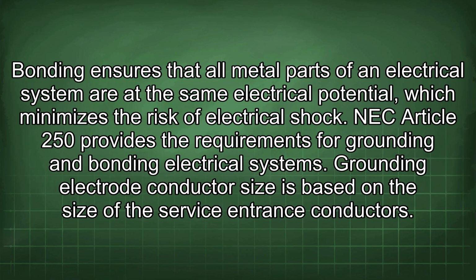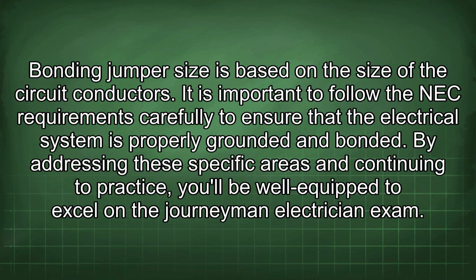Bonding ensures that all metal parts of an electrical system are at the same electrical potential, which minimizes the risk of electrical shock. NEC Article 250 provides the requirements for grounding and bonding electrical systems. Grounding electrode conductor size is based on the size of the service entrance conductors. Bonding jumper size is based on the size of the circuit conductors. It is important to follow the NEC requirements carefully to ensure that the electrical system is properly grounded and bonded.